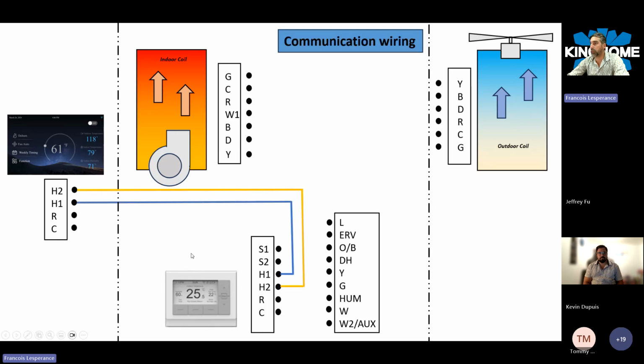The most important thing when you have to troubleshoot these systems is to focus on H1, H2 being connected properly, because there is polarity. Those terminals are polarity sensitive. If they are mixed up, or you have an issue with those wires, we're going to see a communication error showing up on the thermostat as E6 on the touchscreen thermostat, or you'll see the letters C and O on the white thermostat downstairs in the mechanical room. So basically, it's a communication issue, a problem related to the wiring or the terminal connection on H1, H2.